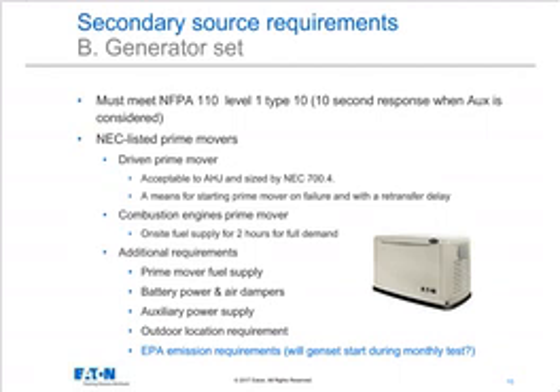There is an outdoor location requirement, and again, we mentioned this earlier, we want to make sure that the generator is located ideally outdoors of the building and not in the basement or in an equipment room, because if the building is involved in a disaster like a fire, we want to be able to access the generator if we have to manually start it, for example.